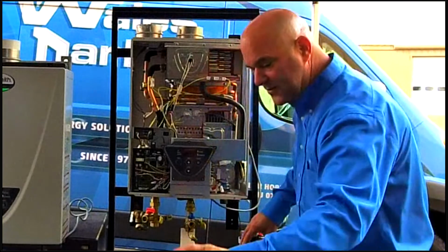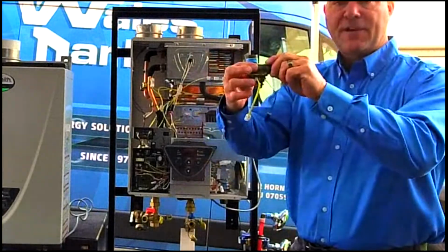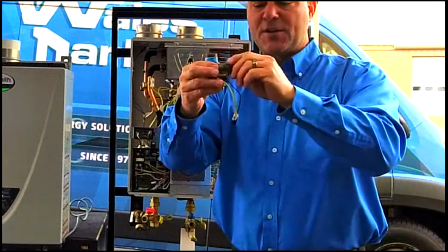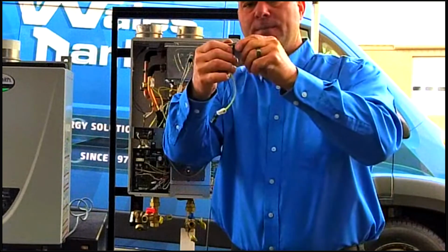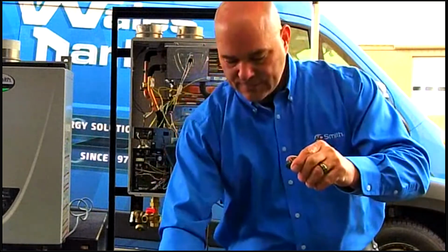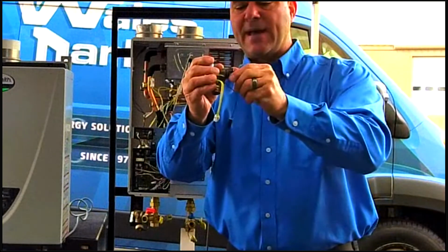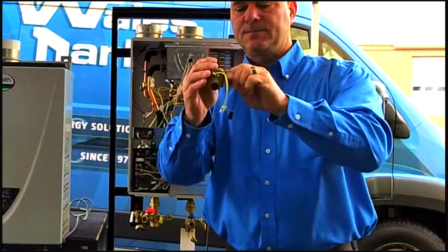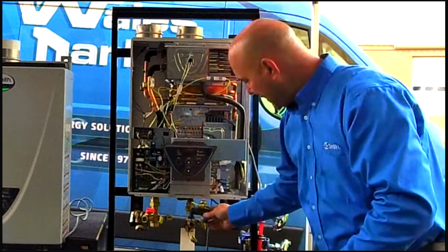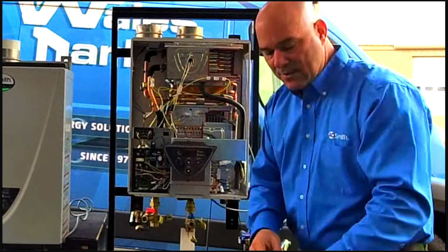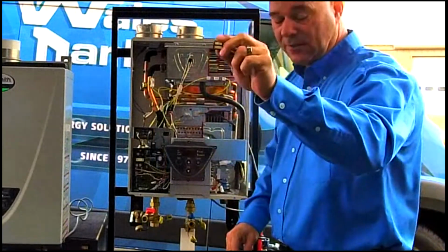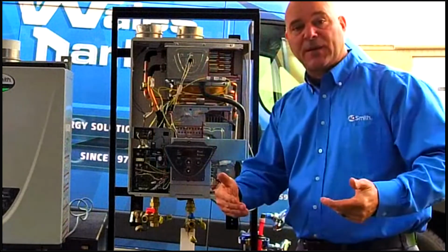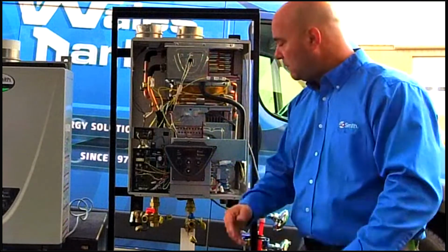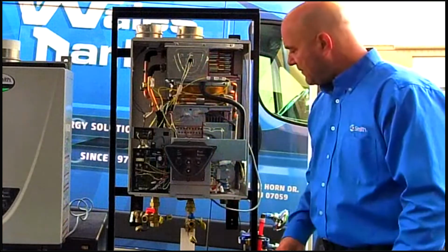You can't see the valve, so I'm going to show you. I would take the valve. I would knock the pressure off, take the valve. I'm going to remove the screen. And then I'm just going to put this back in. Okay? So that's hooked. That's right up inside there. So now I've taken the restriction of my screen, and I don't want that screen to pick up the debris and block my flow. Power's off, obviously.